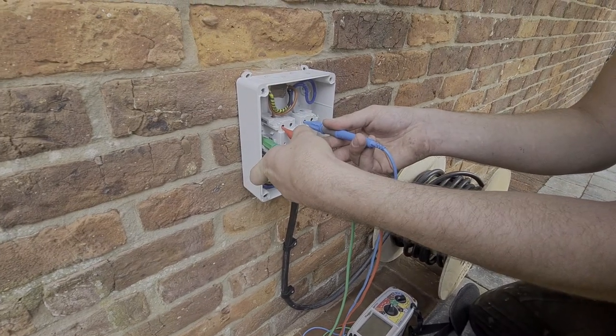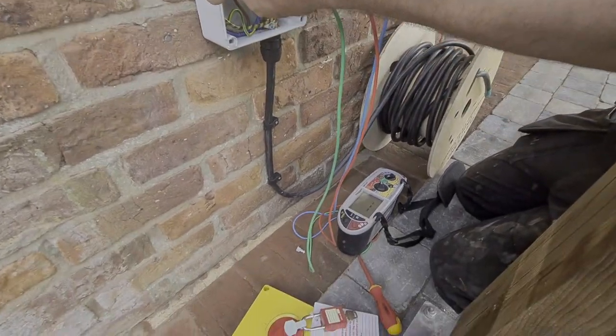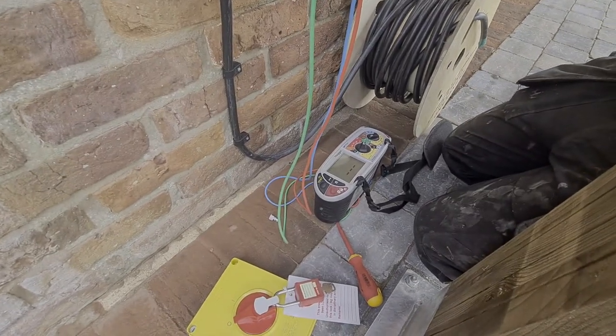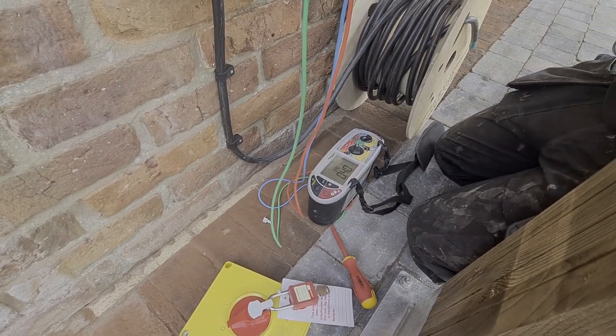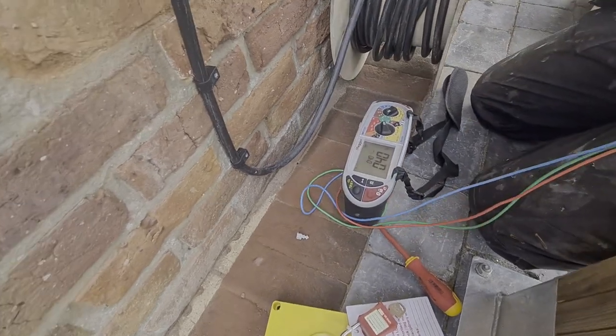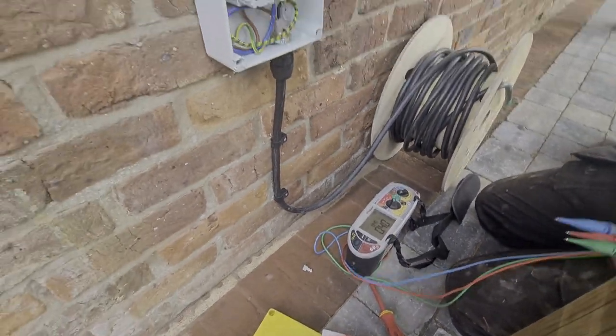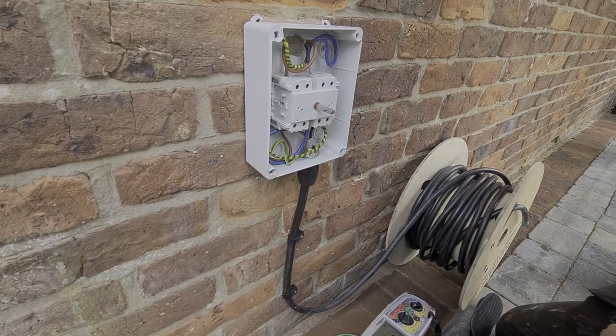We're measuring between line, neutral and the CPC. Just figuring out what it wants. And there you can see we've measured 0.4 ohms, and that's utilizing the supplier's earth.